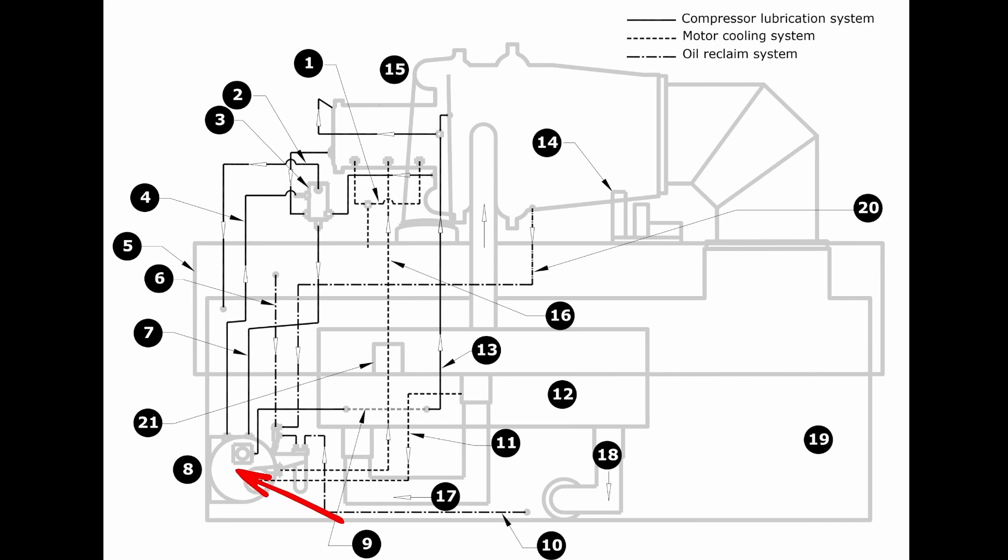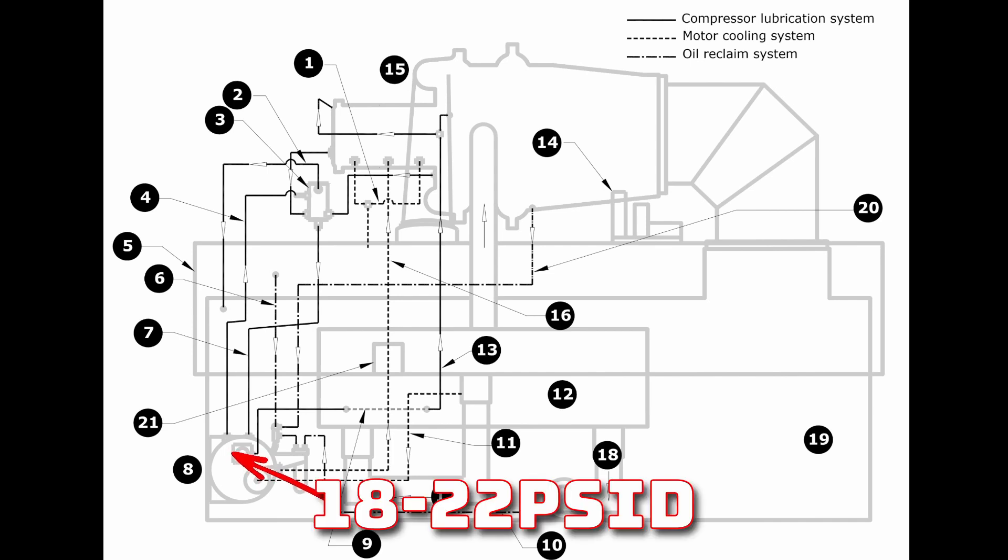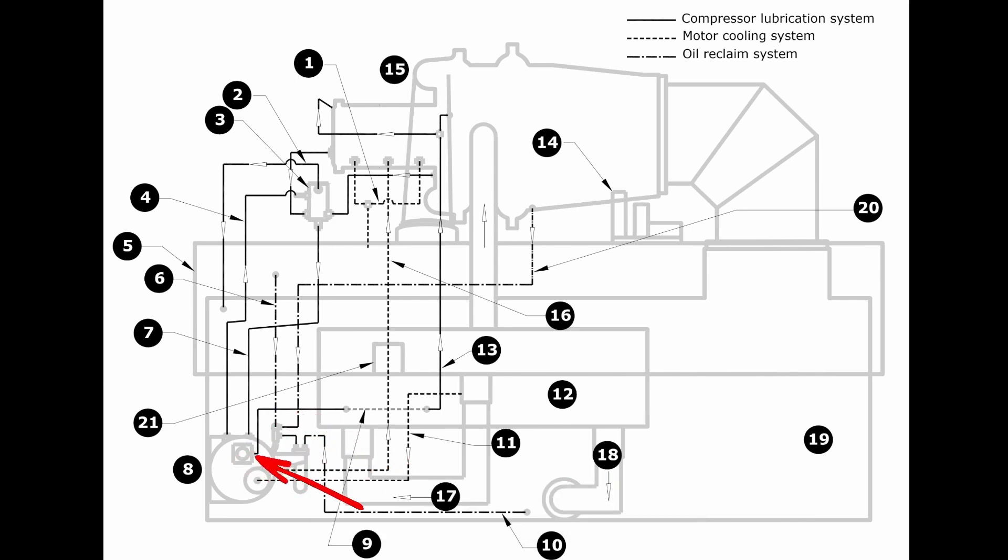This filter regulator block has a canister style filter, very similar to your car, in addition to the physical regulator which is adjustable here at the block. So this regulator will be adjusted to 18 PSI differential between the pump's discharge pressure and the sump pressure.